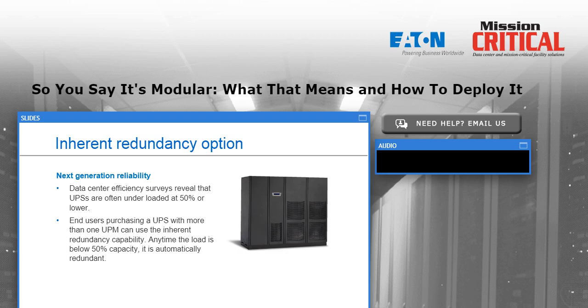If the UPS system, which in this case has 2 of those 300 kilowatt UPMs, it might have 3 or even 4, but in this case, if we have 2, that means if I have less than 50% load at any point in time, I can suffer the loss due to failure or overload of one of those power modules. And if the remaining module is not overloaded, it will remain online and provide conditioned power and battery backup while waiting for the service operation to commence.